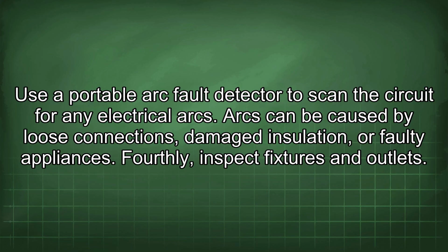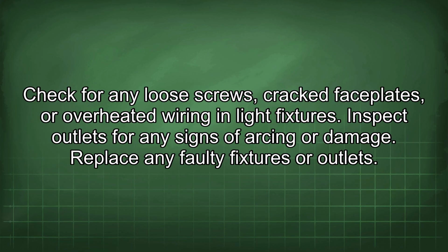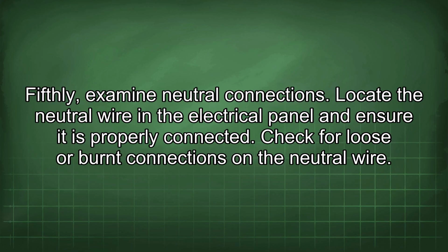Fourthly, inspect fixtures and outlets. Check for any loose screws, cracked faceplates, or overheated wiring in light fixtures. Inspect outlets for any signs of arcing or damage. Replace any faulty fixtures or outlets. Fifthly, examine neutral connections. Locate the neutral wire in the electrical panel and ensure it is properly connected. Check for loose or burnt connections on the neutral wire.